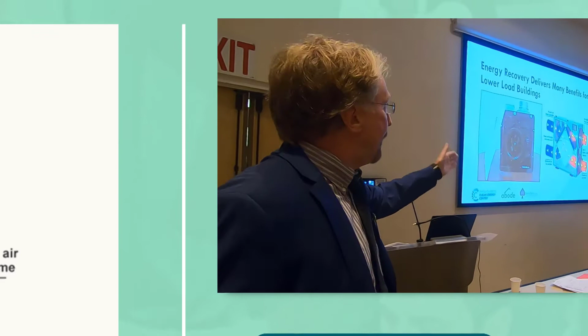The one on the right is the HRV. The difference between the two is the HRV conditions the air that's coming in, preheats it, right? The fan, when every CFM that fan's blowing out, it's ambient air coming in. So when we model these homes, we see that there's a significantly higher heat load when you're just bringing in ambient cold air versus preconditioning with an HRV. So the builders, we just have to know this when we're designing the heat pump system.